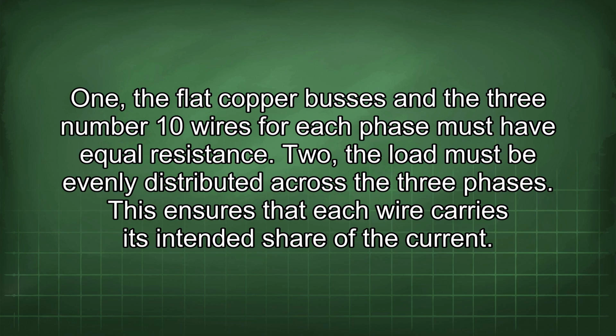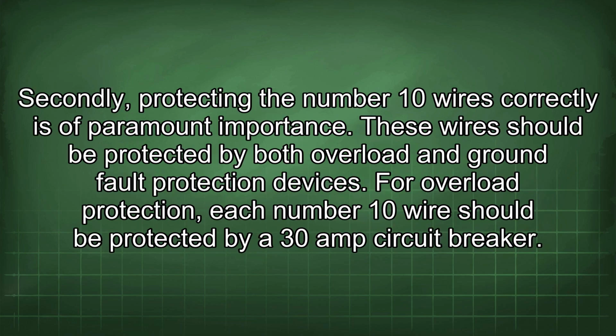2. The load must be evenly distributed across the 3 phases. This ensures that each wire carries its intended share of the current. Secondly, protecting the number 10 wires correctly is of paramount importance. These wires should be protected by both overload and ground fault protection devices. For overload protection, each number 10 wire should be protected by a 30 amp circuit breaker.